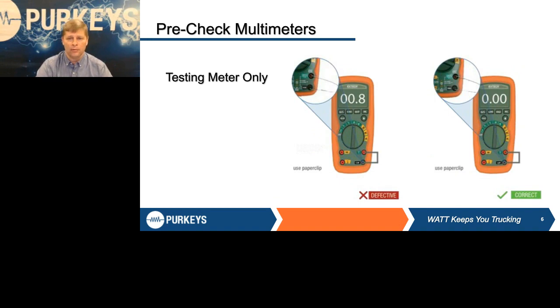We came up with a high-tech tool here years ago. You all know it as a paper clip, but it's a way that you can take your two leads out of the meter, straighten out that paper clip, bend it into a U, and put it where those two meter leads go and check the meter itself. We've taken the leads out of the equation so we know, hey, my meter is good, or hey, my meter is what's defective.